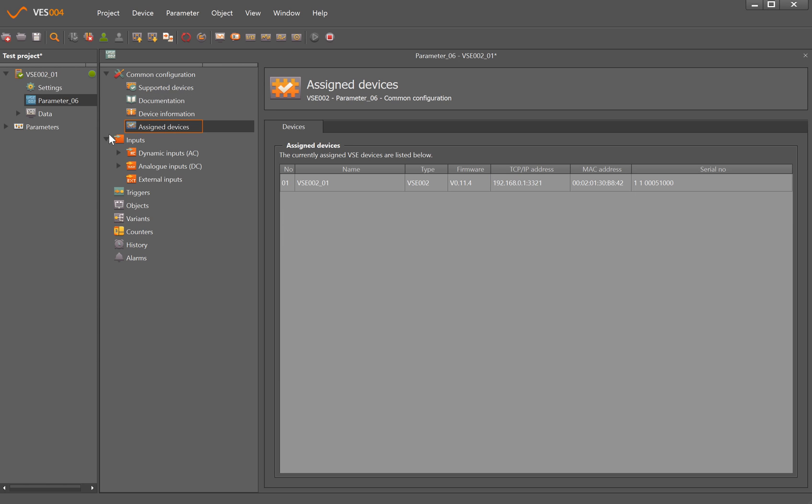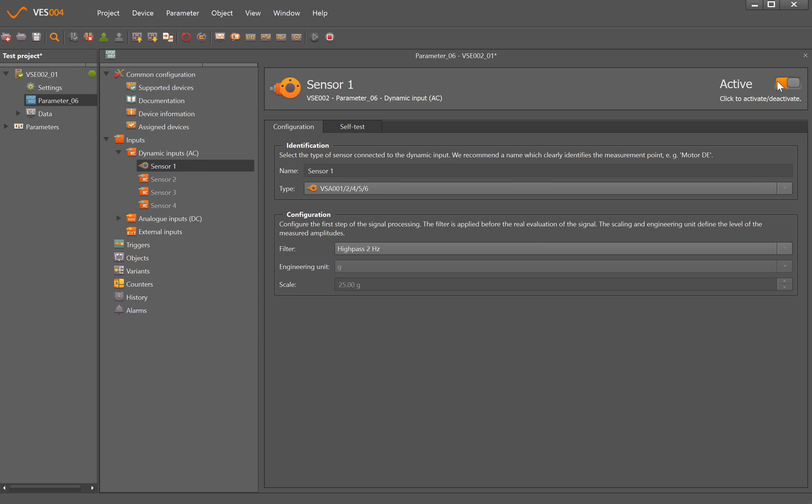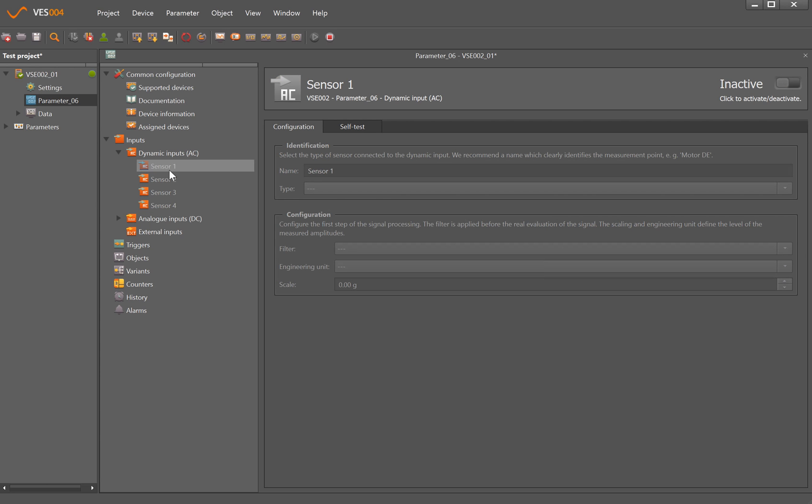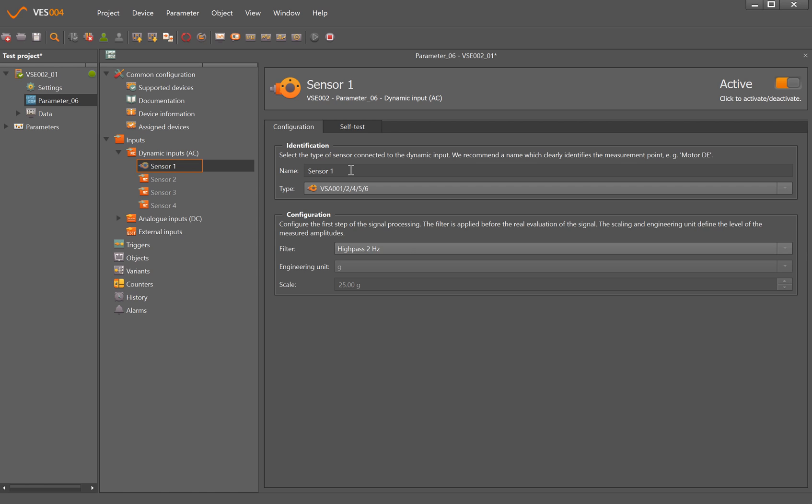But the most important stuff is when we start getting to the inputs. So the first thing you have to tell is how many dynamic inputs - so these would normally be accelerometers. You can either just left click there and then the activate button, or if I right click and click activate there, that's now brought up a window asking me to give it more information about sensor 1. So sensor 1, you can if you want change the name there, so that could be motor drive end, motor non-drive end depending on the location of the machine and also what type of sensor as well.